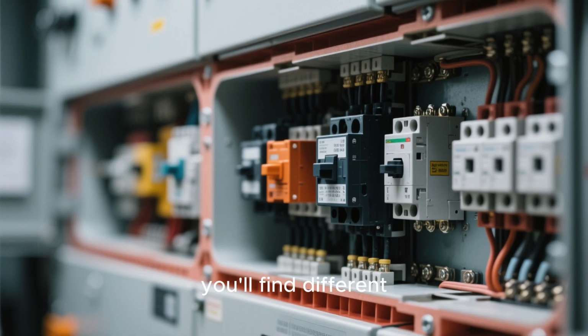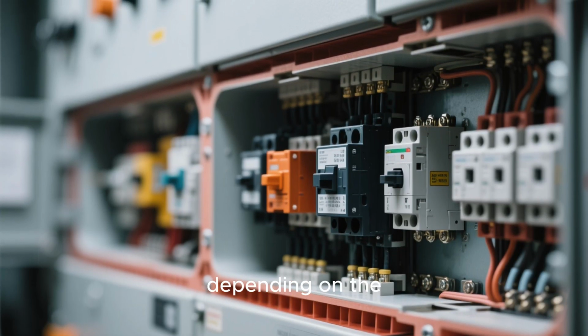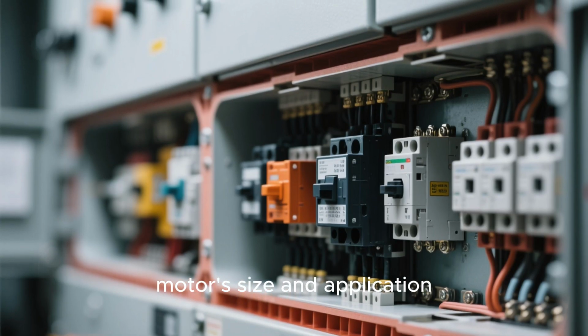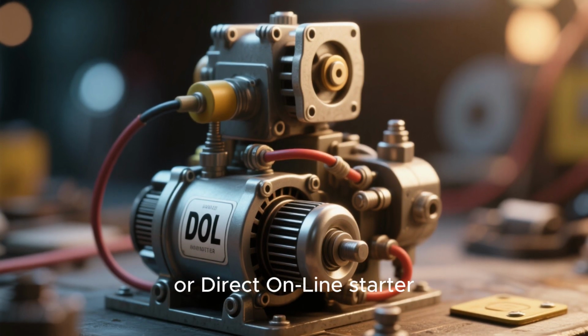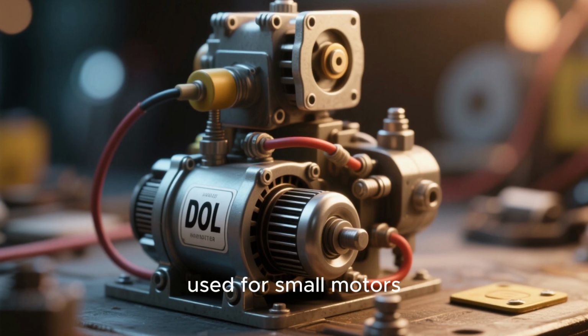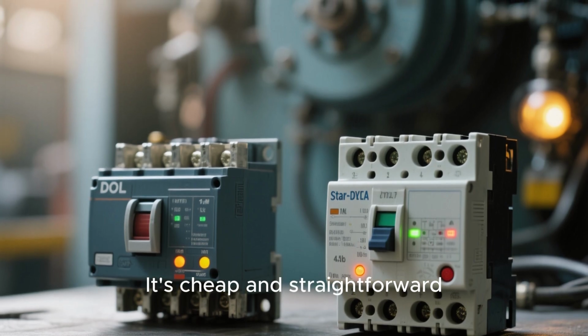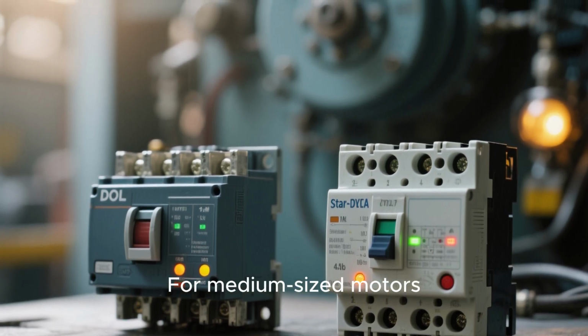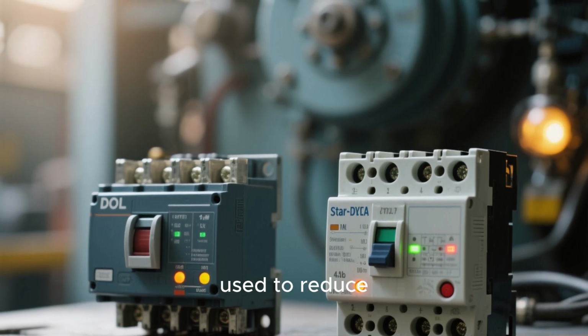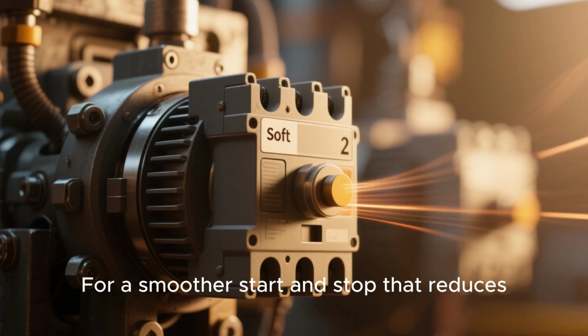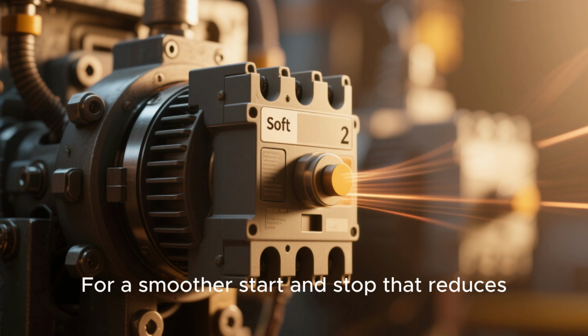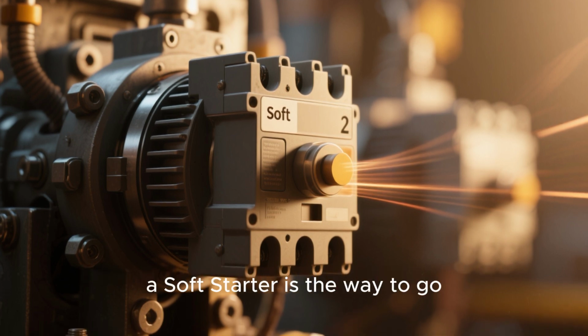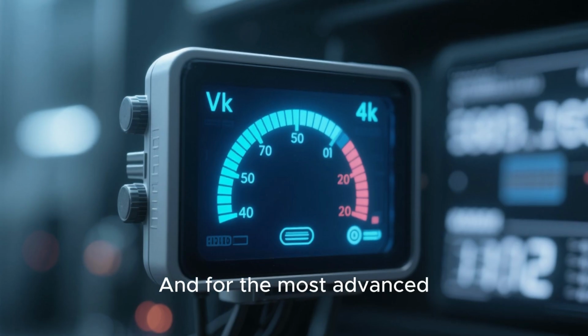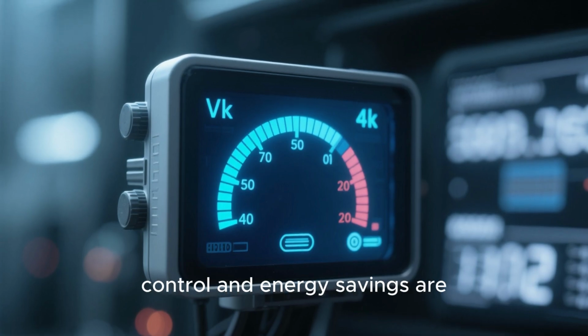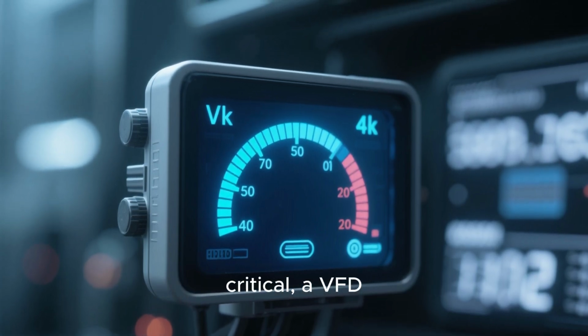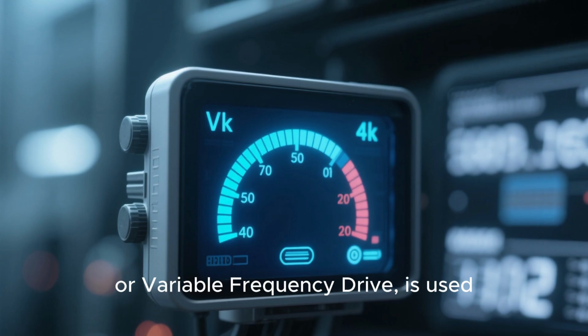Inside these MCCs, you'll find different types of motor starters depending on the motor's size and application. The simplest is the DOL, or Direct Online Starter, used for small motors. It's cheap and straightforward. For medium-sized motors, a star delta starter is often used to reduce the high starting current. For a smoother start and stop that reduces mechanical stress, a soft starter is the way to go.